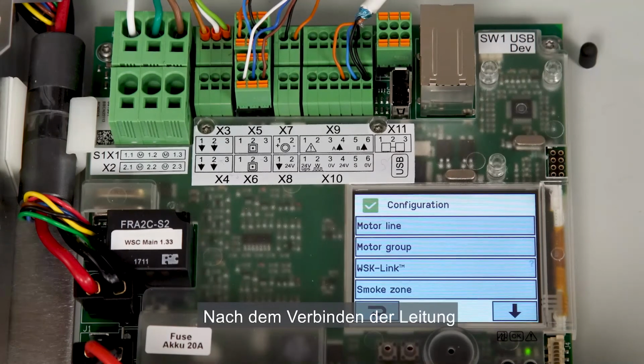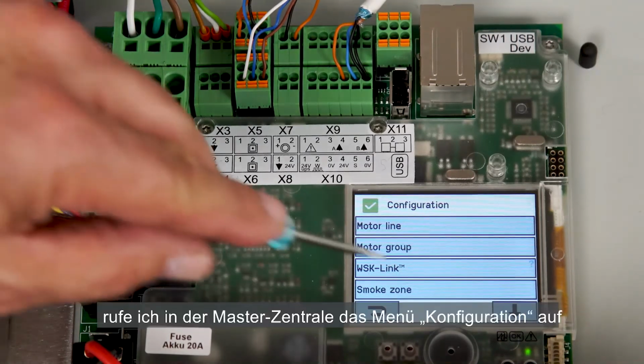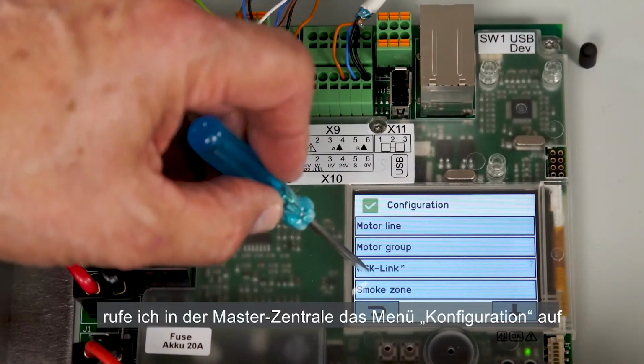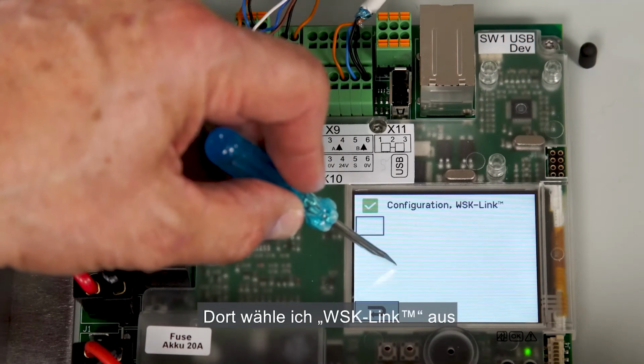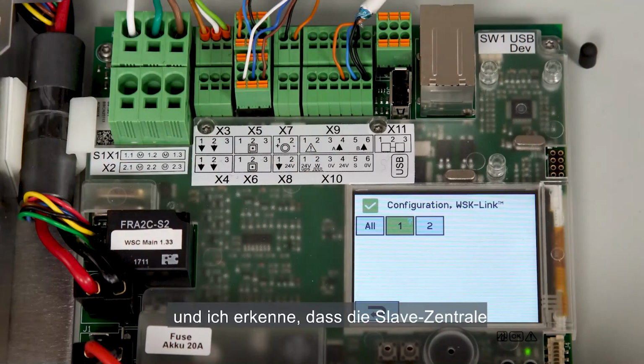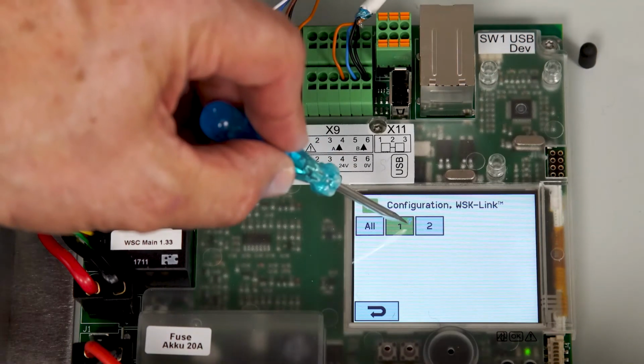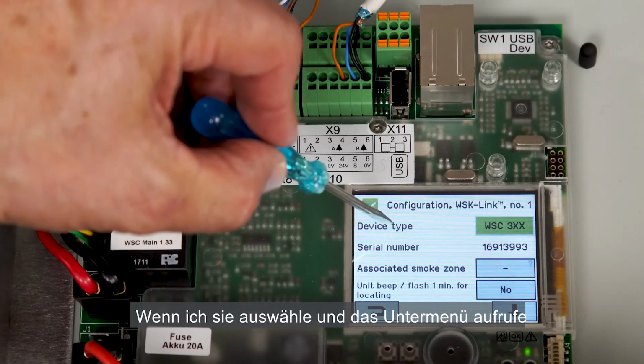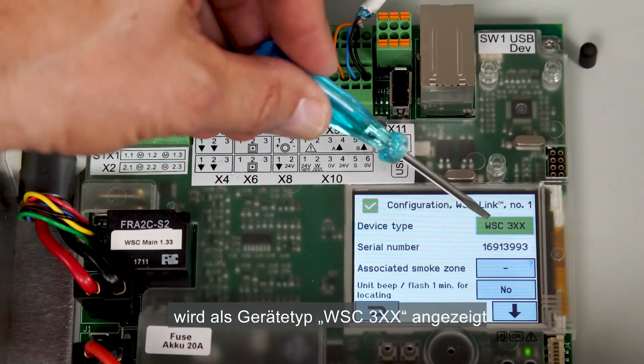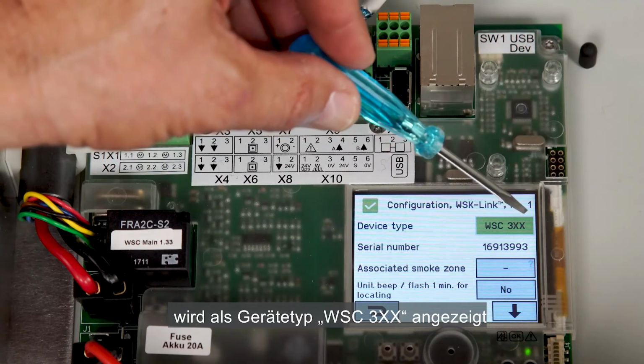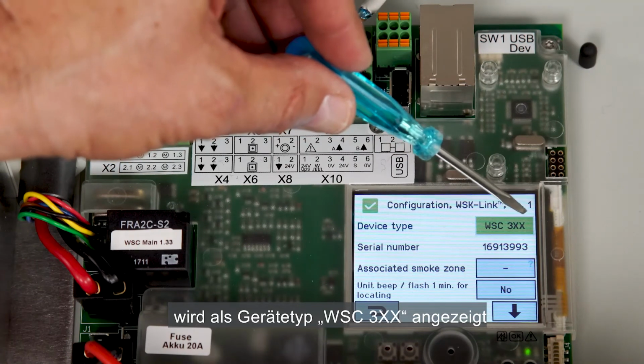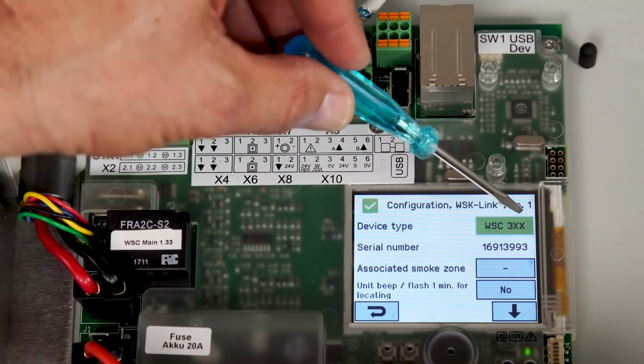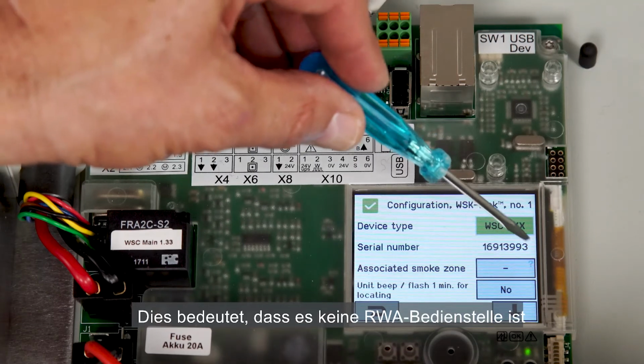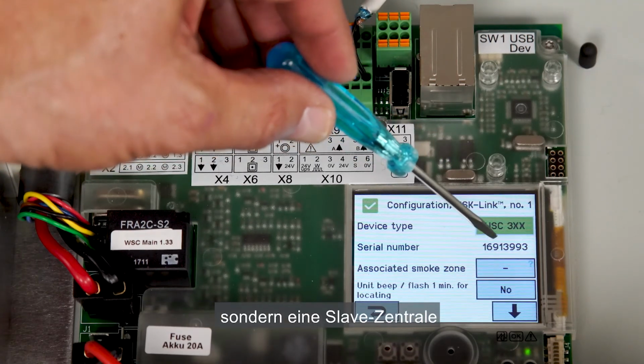After connecting the cable in the master panel, I go into the configuration menu and select WSK Link. And I can see that the slave panel is represented as another break glass unit. If I select it and go into the submenu, I see that the device type is WSC3XX. This means that this is not a break glass unit, but a slave panel.